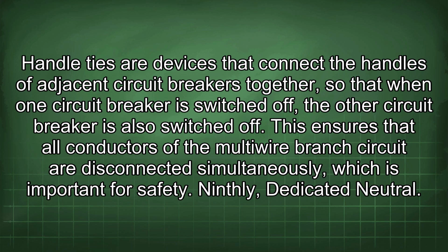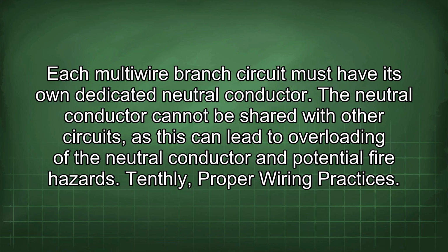This ensures that all conductors of the multi-wire branch circuit are disconnected simultaneously, which is important for safety. Ninthly, dedicated neutral. Each multi-wire branch circuit must have its own dedicated neutral conductor. The neutral conductor cannot be shared with other circuits, as this can lead to overloading of the neutral conductor and potential fire hazards.